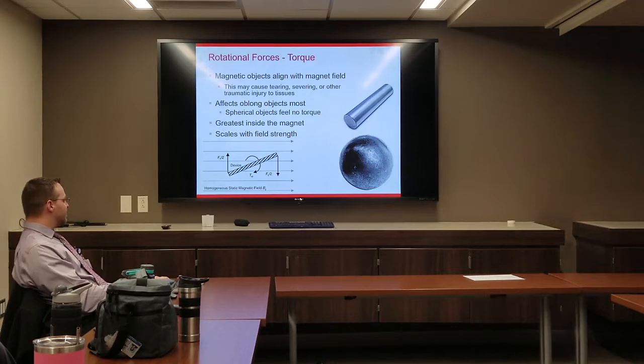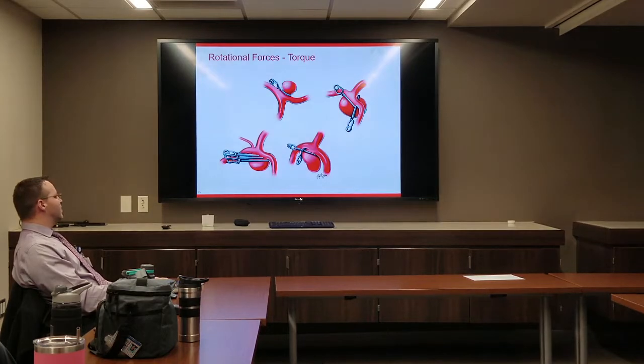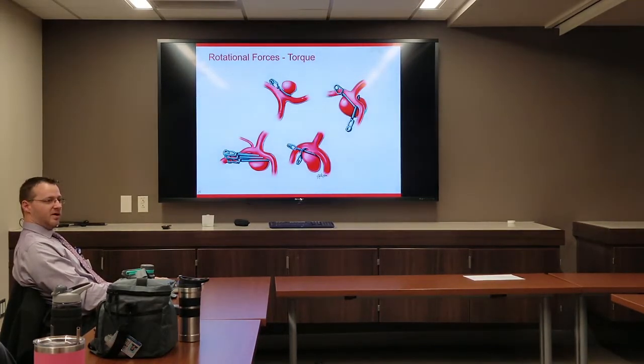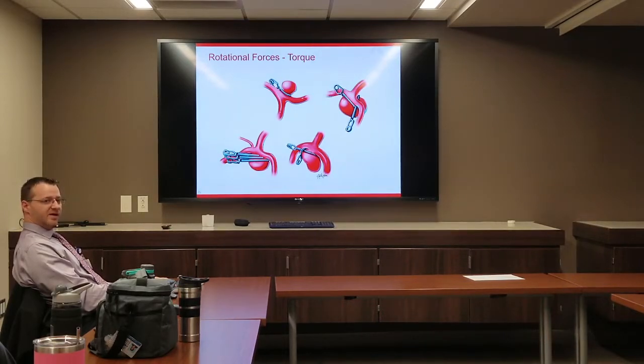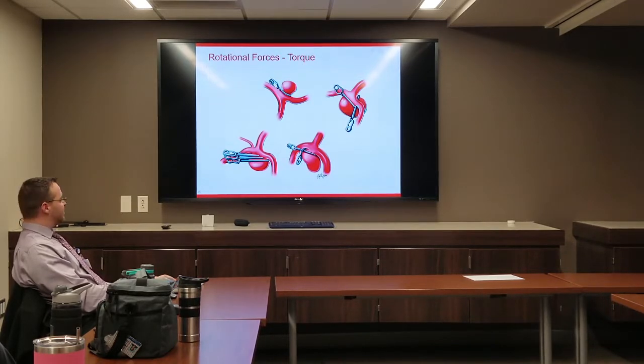Torque does scale with field strength, so at 3T it's going to be stronger than at 1.5T. A common consideration is aneurysm clips — even though clips are small, if they're slightly ferromagnetic, they could twist to align with the field, which could actually sever the aneurysm vessel. This is one reason you want to screen for these materials very closely.